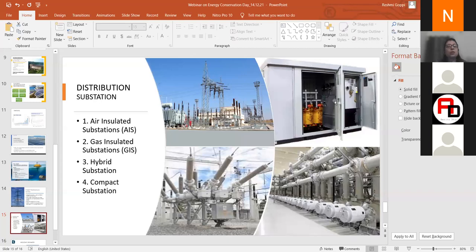And the compact substation, normally we see this in the distribution part, for the low voltage part, that is 11 kV or less. One part is the transformer, then a busbar chamber, and another part is the RMU chamber, where the isolator and circuit breaker are. It is very space saving.